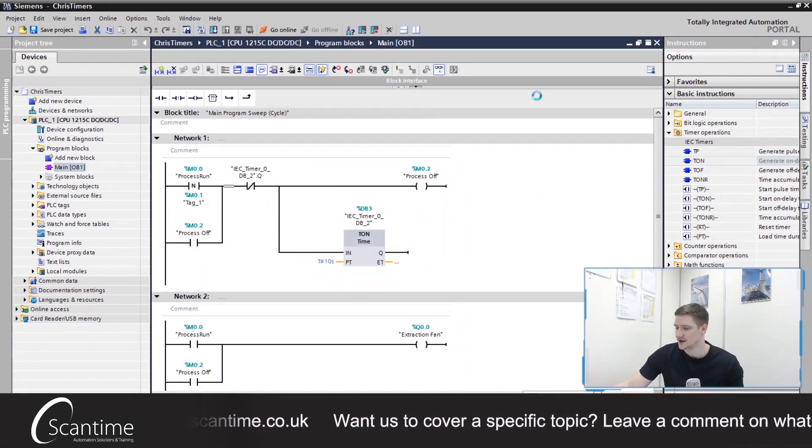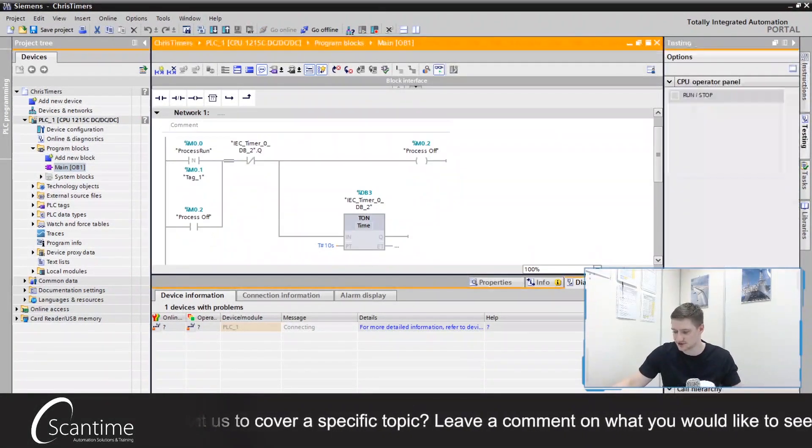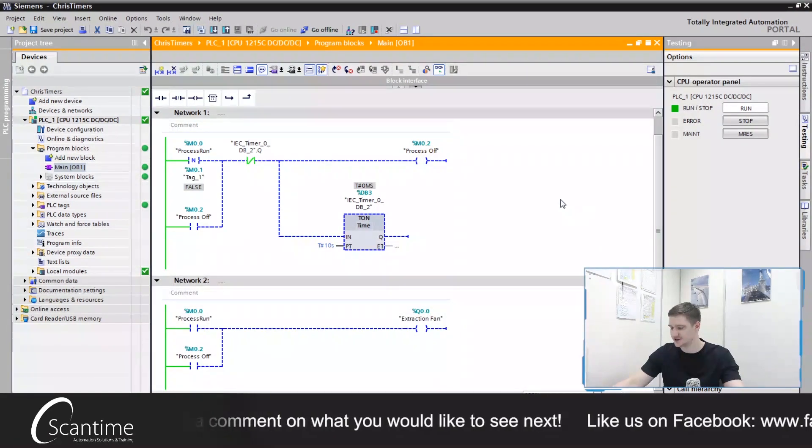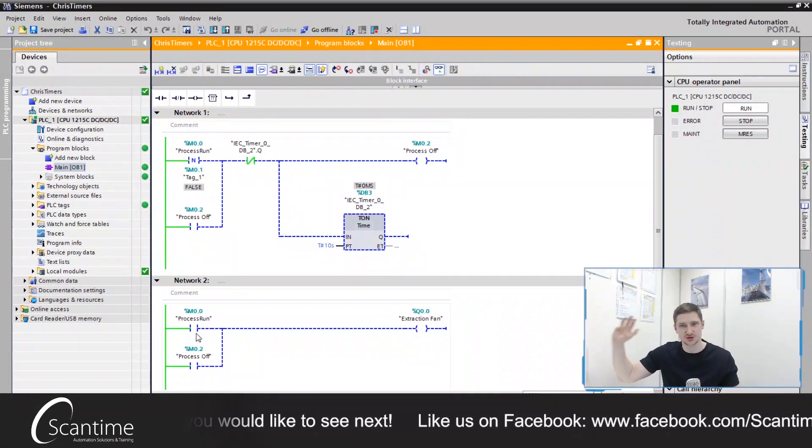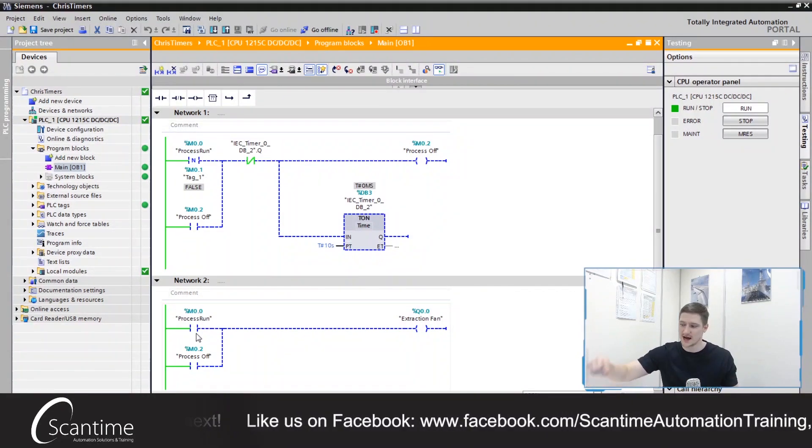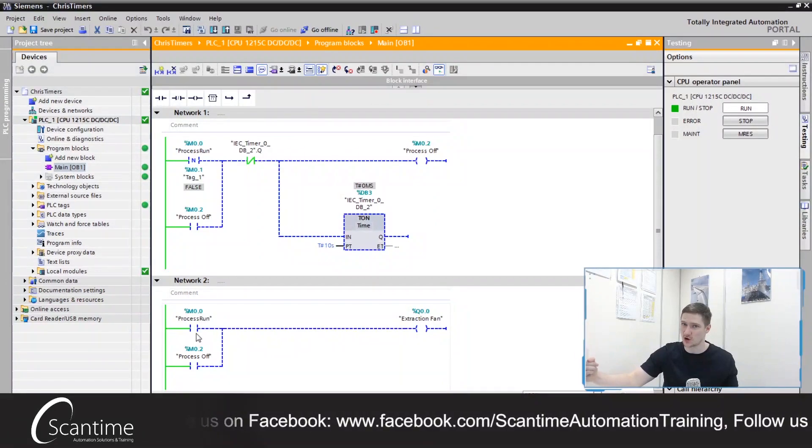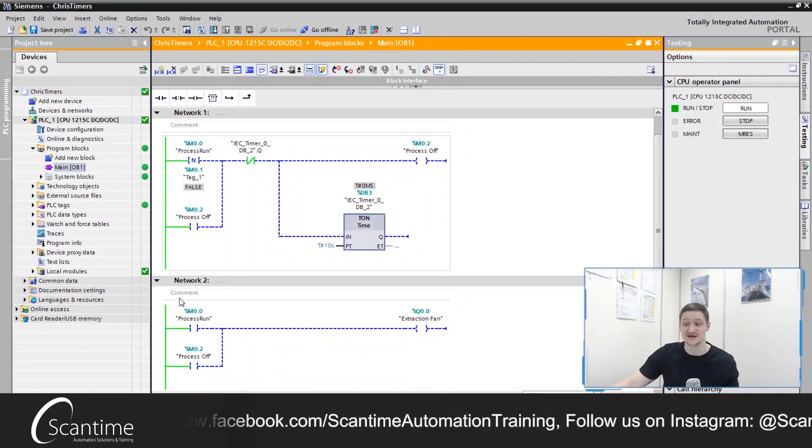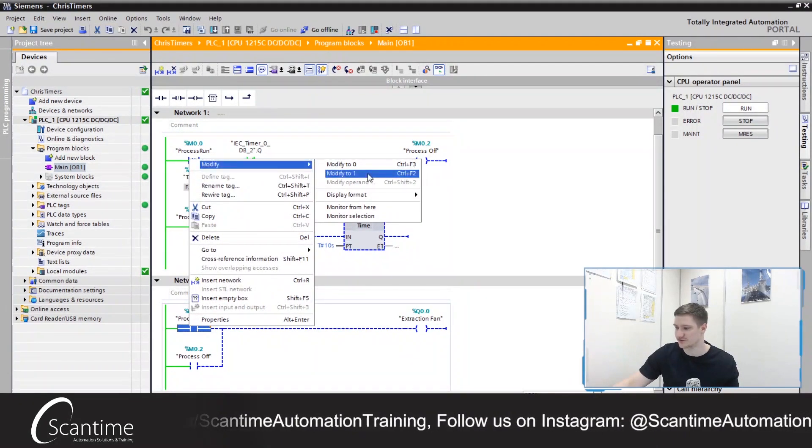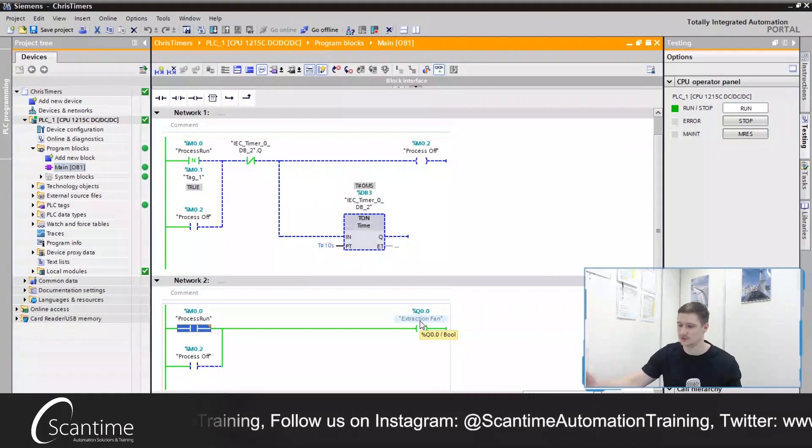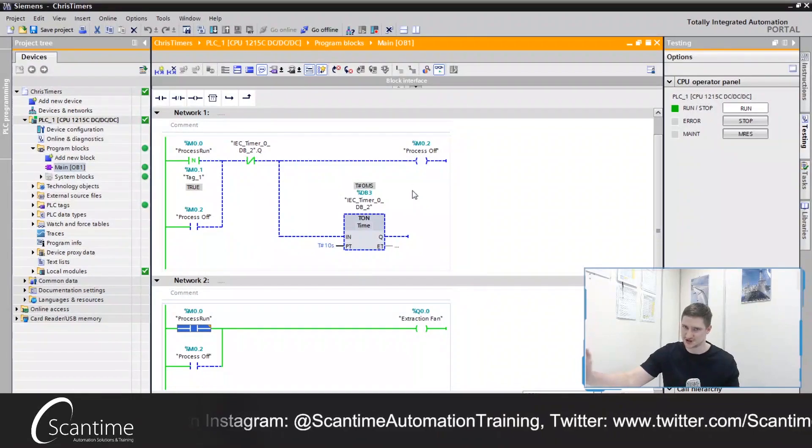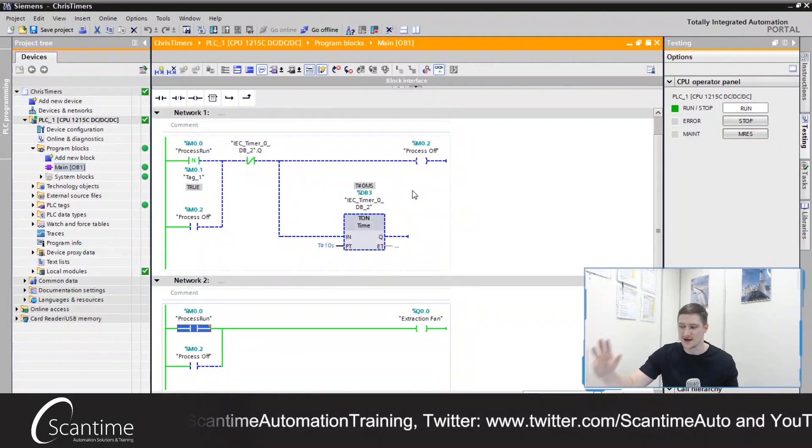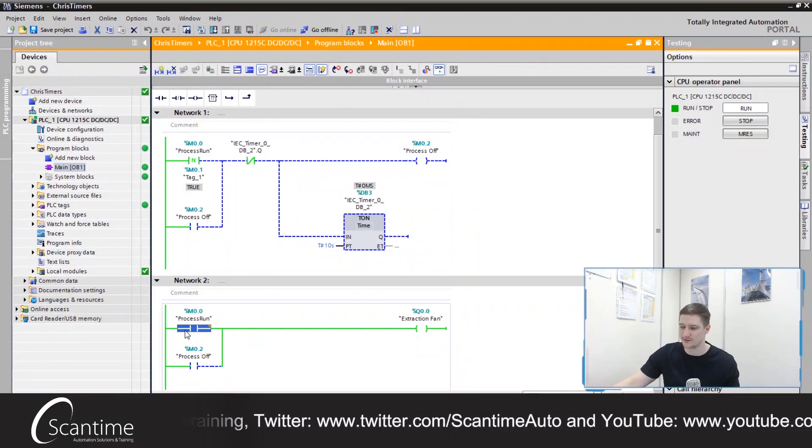Let's go online. Let's minimize all the networks and these little boxes at the bottom. So when the process run turns on, the extraction fan turns on. When the process run turns off, our extraction fan stays on for 10 seconds. Let's see if this works. Right click the contact, modify it to 1. Our extraction fan is currently on, which is what we should be seeing. At the moment, nothing is running, which is exactly how that TOF runs. It only kicks into gear when the process turns off.